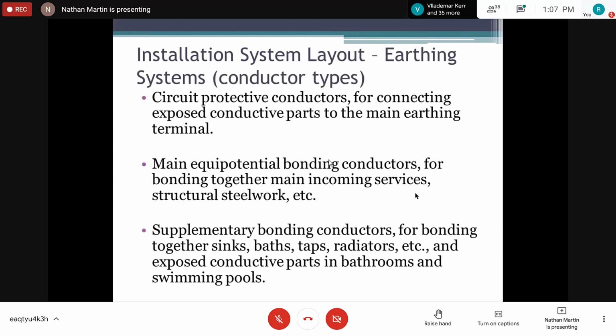Now, conductor types used to earth. If you are talking about your service conductor, we also can calculate the size of your earth, right? Typically, what electricians, engineers or technicians will do is size the earth conductor similar to the phase conductor, and that will take care of any calculation, right?